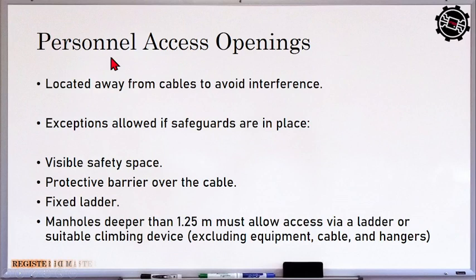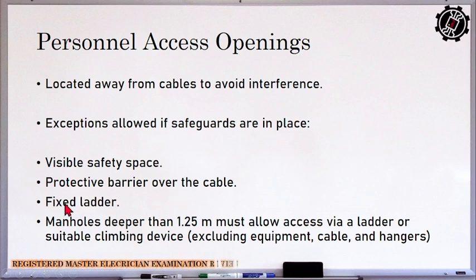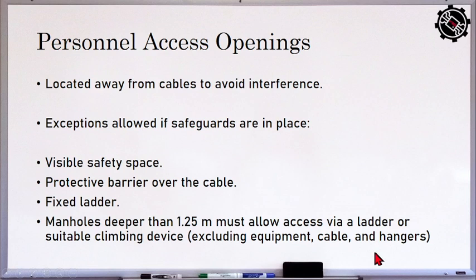Okay. So personnel access opening, located away from cables to avoid interference, no? So exceptions if safeguards are in place. The safeguards must be visible, safety space, mayroon siyang protective barrier, mayroong fixed ladder, tapos manholes deeper than 1.25 meter must allow access via a ladder or suitable climbing device, no? So either that is cable or hindi po kasama pala yung equipment, cable at hangers.